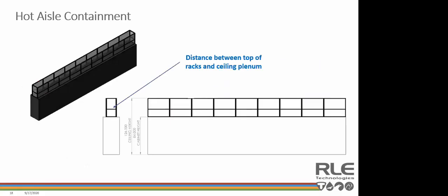In some cases, the hot aisle can be just one row of racks. We were recently approached by a customer utilizing high-density racks, some of them loaded to 21 kilowatts per rack. The racks exhausted the heat out the top of the rack, so a full aisle containment solution wasn't required. But hot air exhaust still needed to be contained on its way back to the cooling unit, simply because the return air temperatures were between 115 and 100 degrees Fahrenheit. The solution was just a simple chimney which added to the top of the racks, allowed for the hot air to escape from the rack into the ceiling return air plenum and all the way back to the cooling unit. This is just one example of how aisle containment can be flexible to suit the customer's needs.